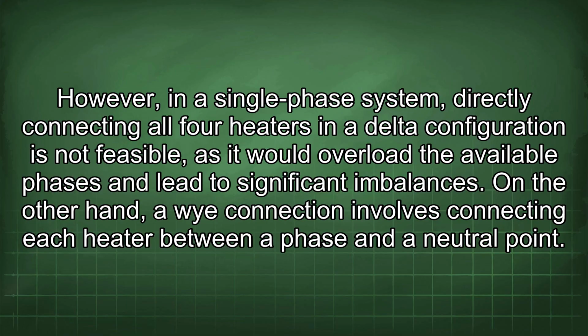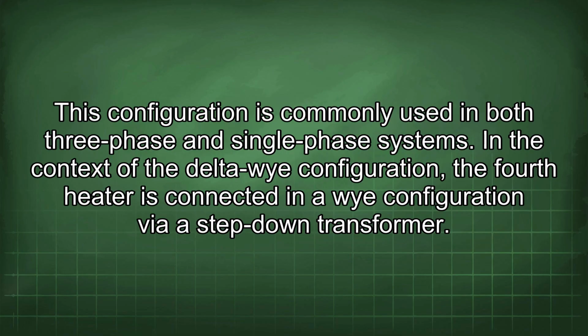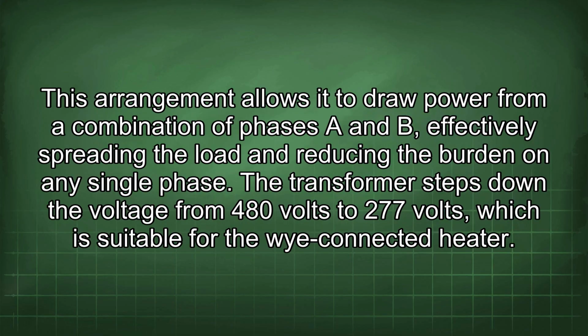On the other hand, a Y connection involves connecting each heater between a phase and a neutral point. This configuration is commonly used in both 3-phase and single-phase systems. In the context of the Delta-Wye configuration, the 4th heater is connected in a Y configuration via a step-down transformer. This arrangement allows it to draw power from a combination of phases A and B, effectively spreading the load and reducing the burden on any single phase.